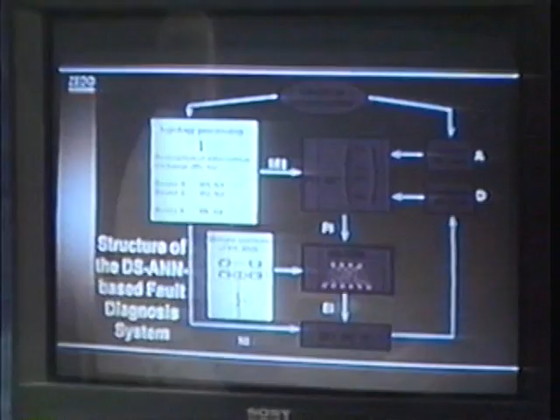It can be done offline, and the matrices Mi and Ni afterwards describe how the alarms and the intermediate diagnoses have to be used as input data for a certain device-specific artificial neural network doing the fault diagnosis, for example, for a certain line. It's worth mentioning that for lines there is only one artificial neural network doing that fault diagnosis. We do not have to train artificial neural networks for each line, but the same trained network can do the fault diagnosis for all lines subsequently, just by making sure that the input vector is related to a certain line. Then the network generates the diagnosis related to that very line.